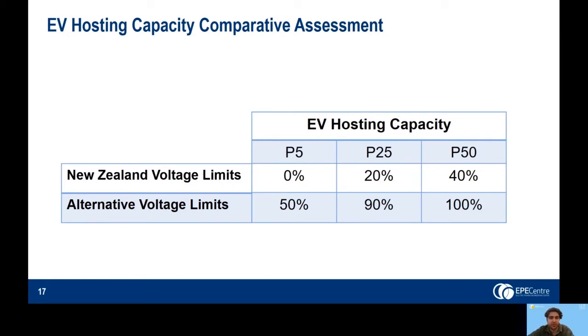So we can see if we use the most conservative hosting capacity, that is the P5 value, when using the New Zealand limits, the hosting capacity is 0%, i.e. the network can't accommodate any EVs. Whereas if we move to the alternative limits, even when using the P5, the hosting capacity is now 50%.